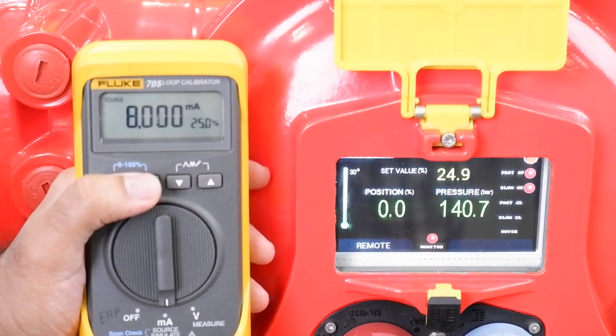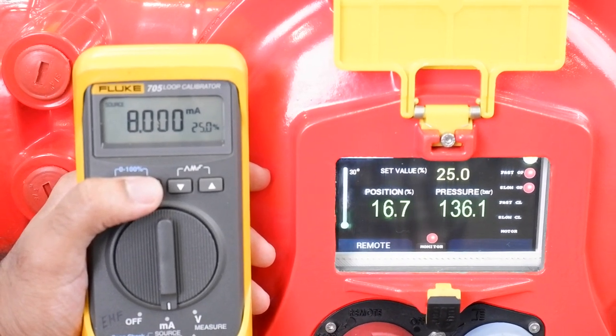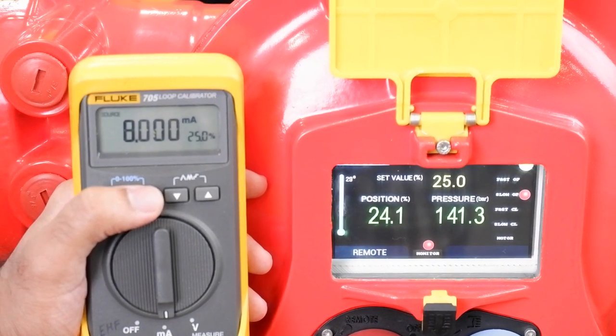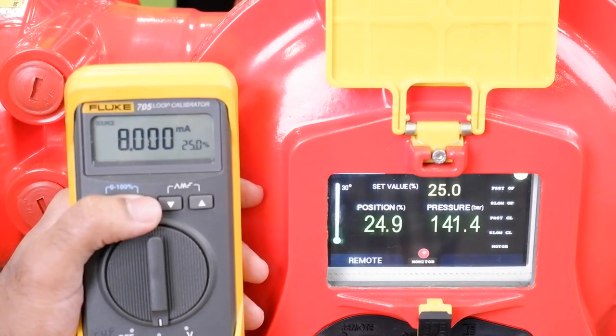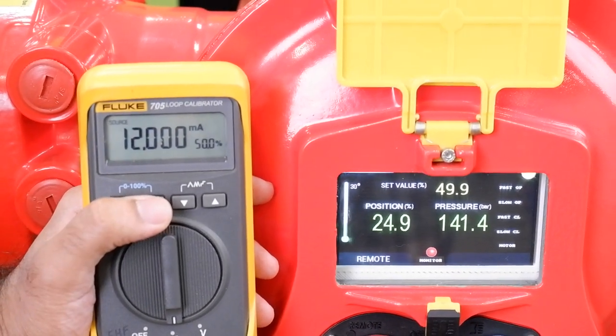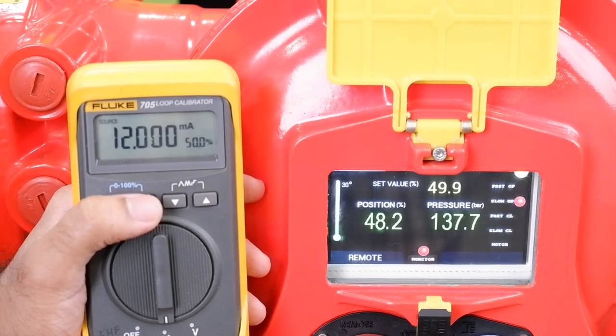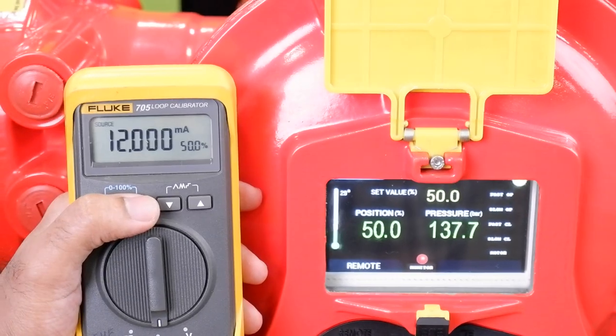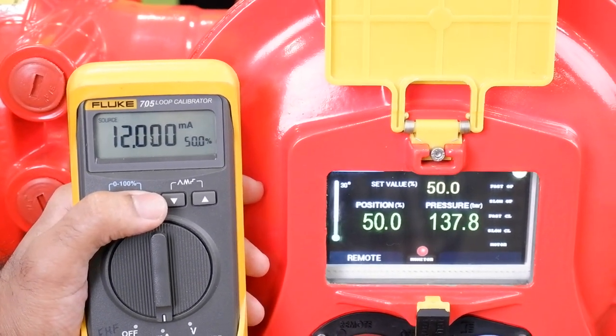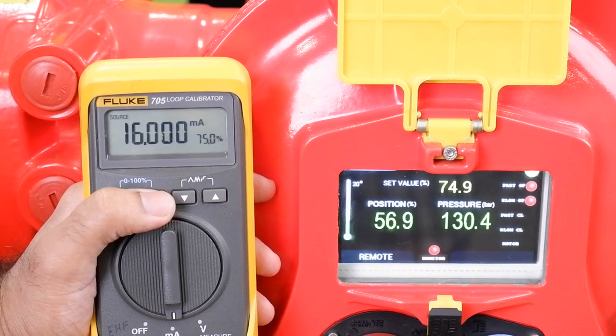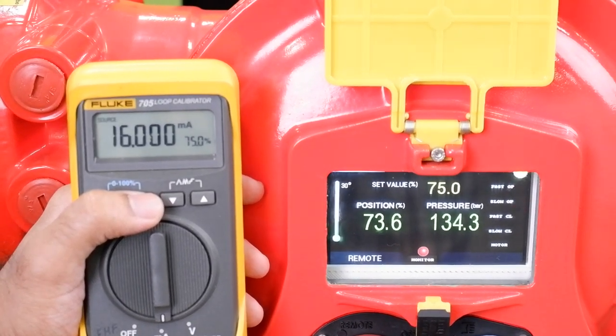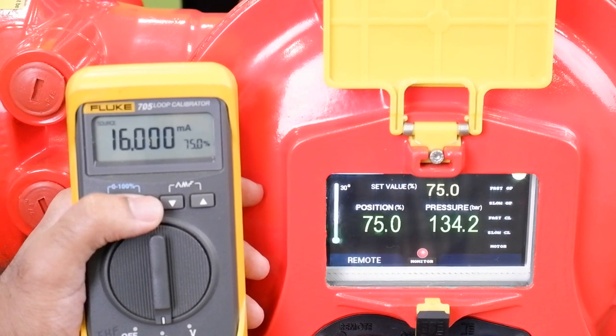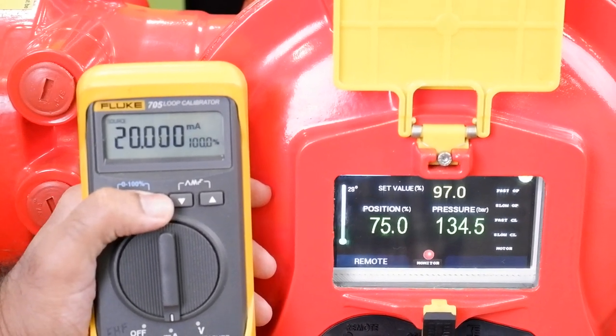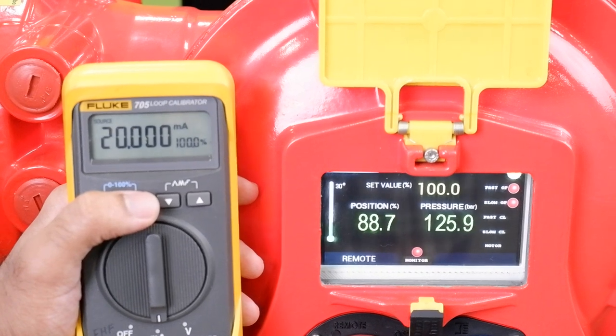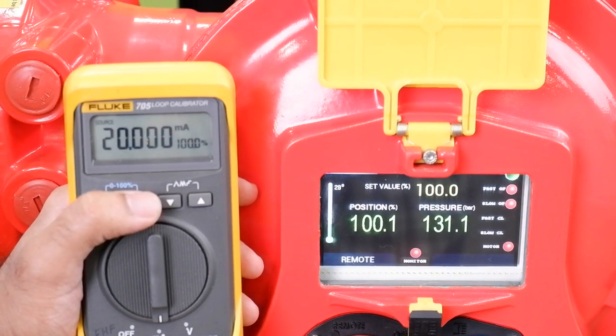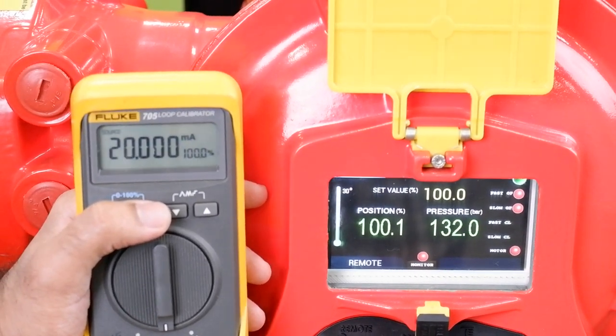I am giving 25% input, 8 milliampere, the valve has opened to 25%. I am giving 50% input, 12 milliampere, and the valve has opened 50%. Now 75% input, and the valve has opened 75%. And now 20 milliampere means fully open. The valve has opened fully in tight shut off.